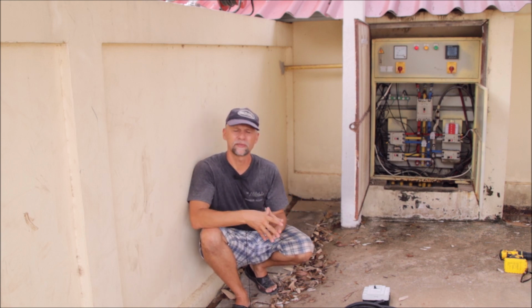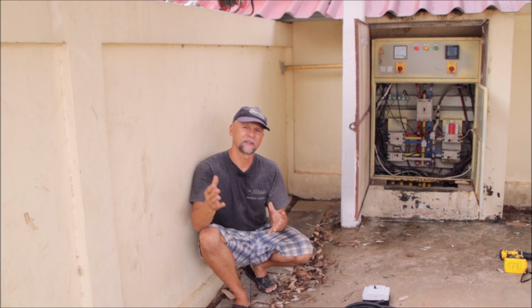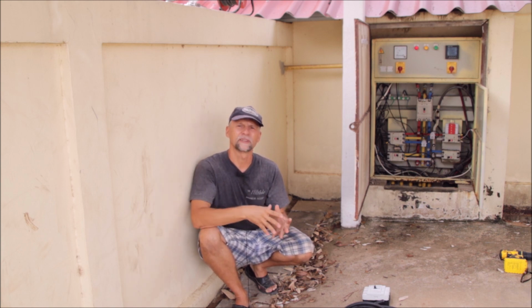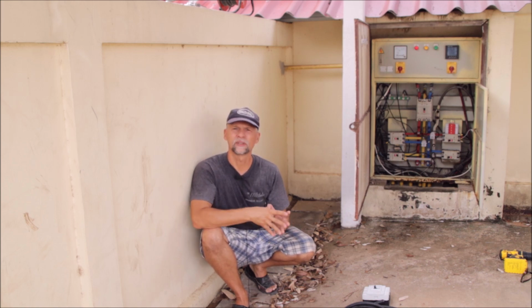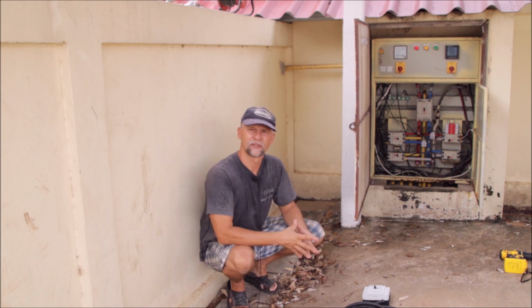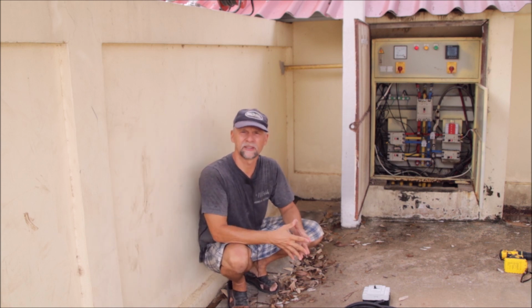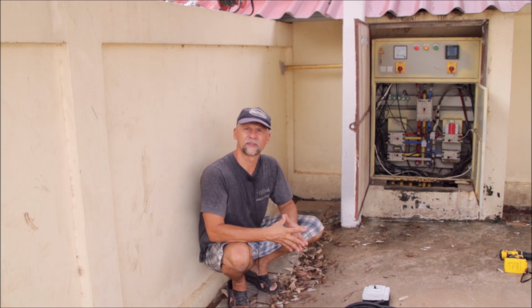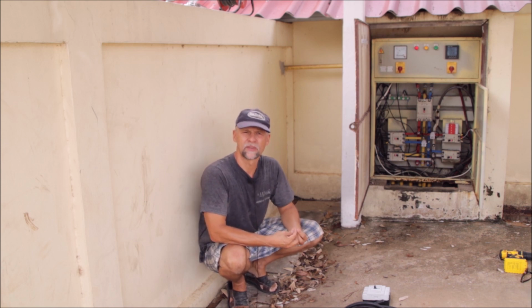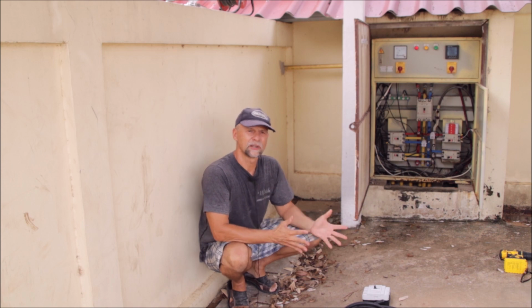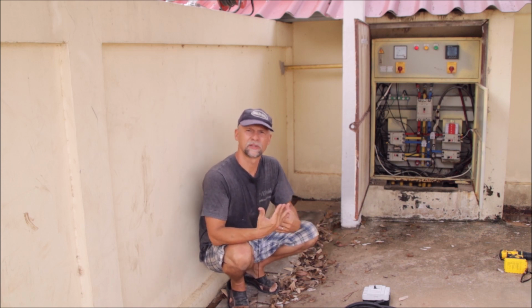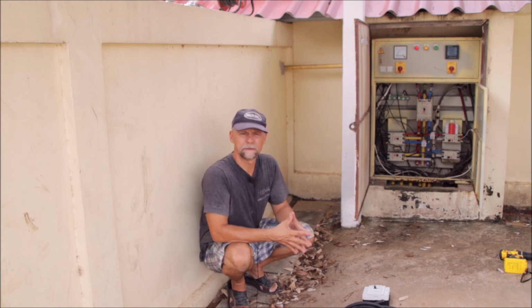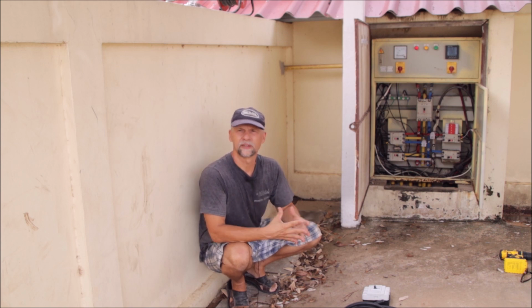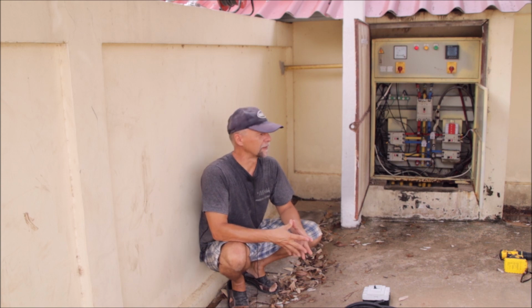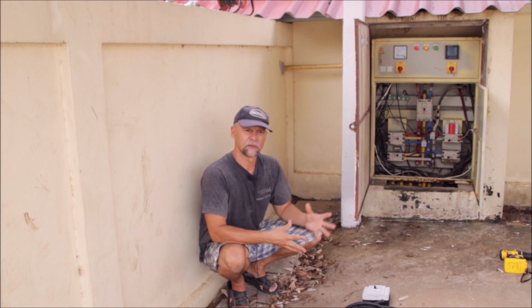So for example, this 3-phase 100 amp breaker is protecting 10 square millimeter wires, which are 110 meters long. If we now look up what resistance a cable of that length and diameter has: the current goes 110 meters there and 110 meters back, so the cable length for the short circuit is 220 meters, and that cable would have a resistance of around 400 milliohms. If that short occurred between a phase and a neutral wire, this would cause around 550 amps of short circuit current. 550 amps on a 100 amp breaker.